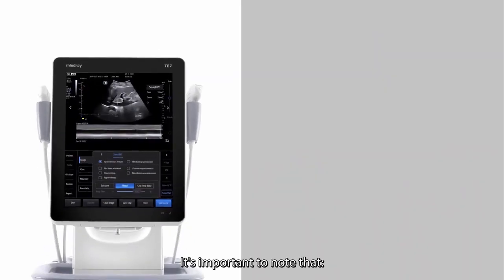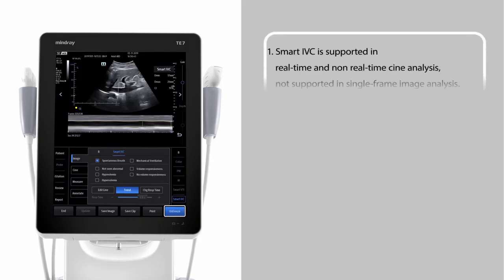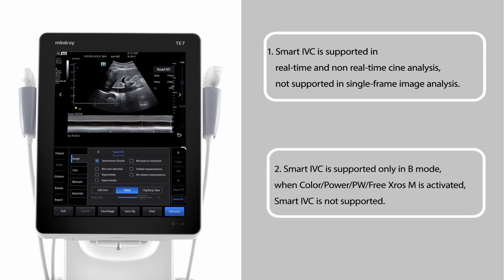It is important to note that Smart IVC is supported in real-time and non-real-time cine analysis, but not supported in single frame image analysis. Smart IVC is supported only in B-mode.